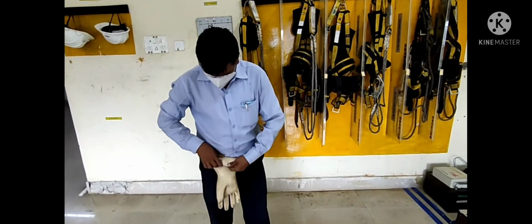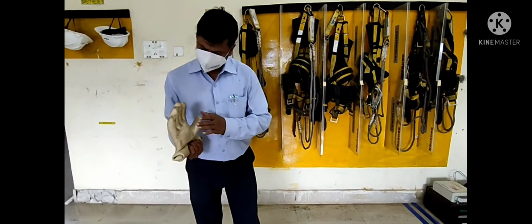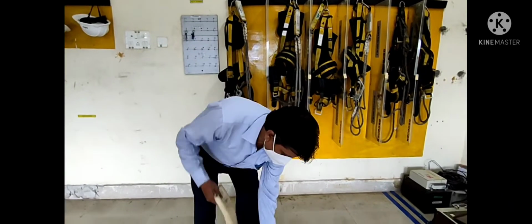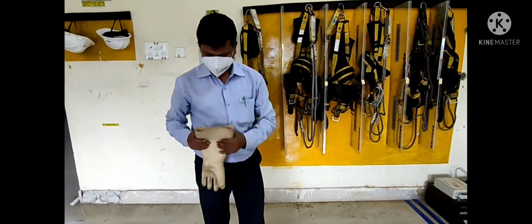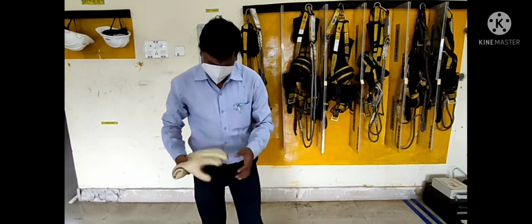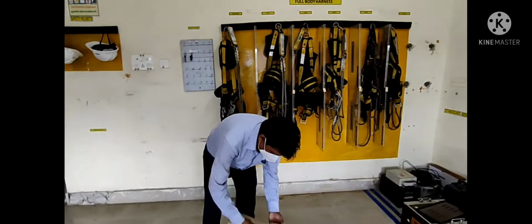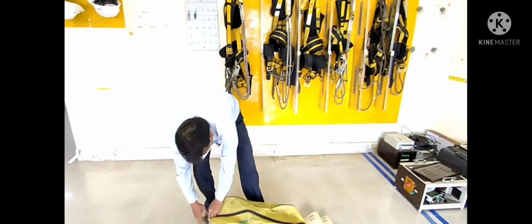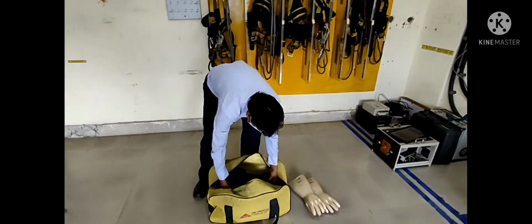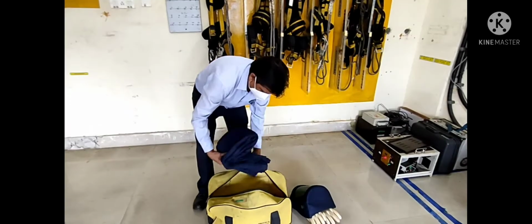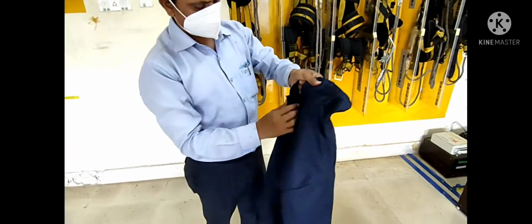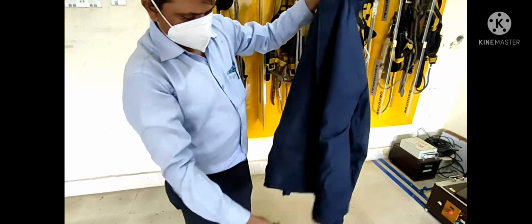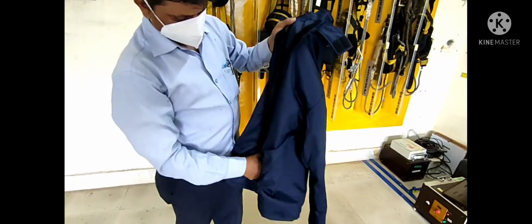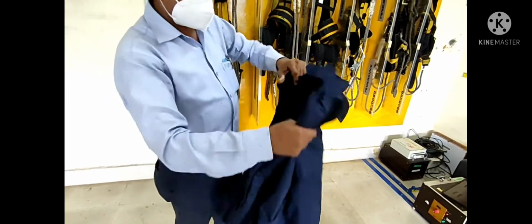Before wearing the gloves, you have to inspect them. For that, roll the gloves up about 1.5 inches. Then squeeze them and hold them up to your ear. If you feel anything, you should destroy it and throw away the gloves. Now you have to inspect your arc flash suit. For that, inspect all garments for contaminants and cuts as you put them on.